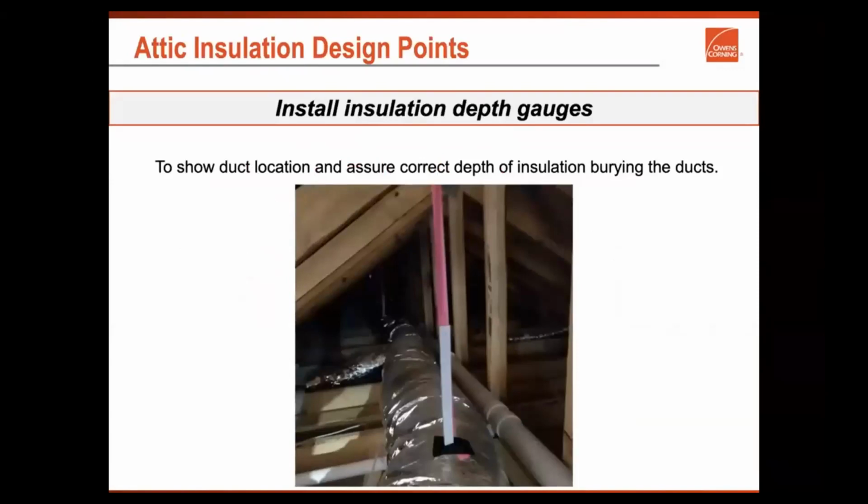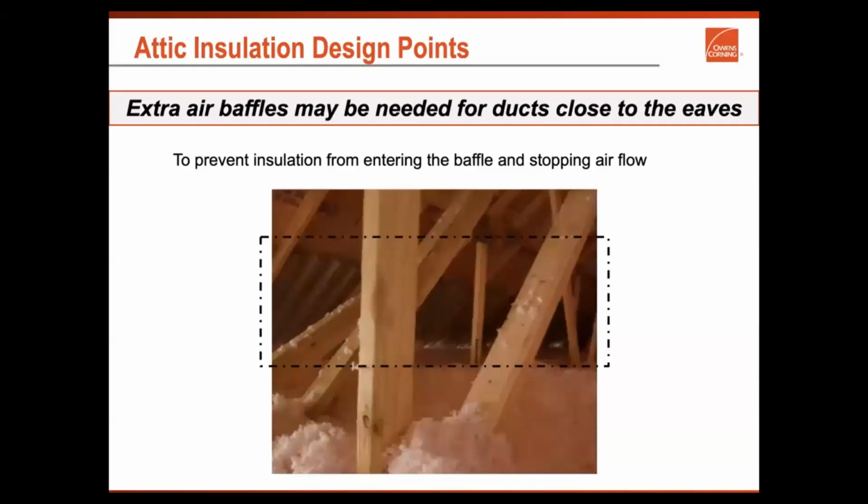So once again, here's another picture of an attic ruler with a simple system. There's no patent on it. It's simple, it's easy. People can read it and see it. And as you can see, this trunk is crossing a bunch of truss cords, but as soon as that intersection comes where that register is going to come off of it, it's going down immediately onto the gypsum. So that's crucial when talking about it. And of course, baffles to prevent airflow from moving the insulation.